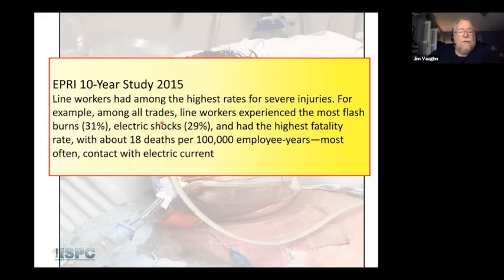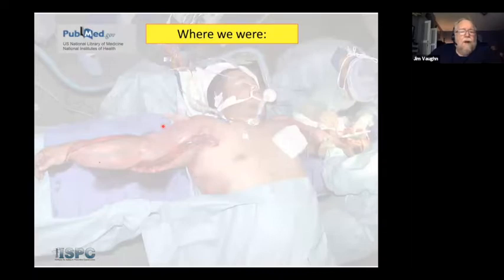to induction hazards, because as third party investigators, and also as legal advisors in electric cases or utility cases against OSHA, what we can tell you is that it seems that we're moving away from direct contact, but we're getting more and more injuries because of induction injuries on grounded circuits. But that doesn't eliminate the risk that's out there for improper cover up. So I'm encouraging you in the hardest way to recognize that there are risks.